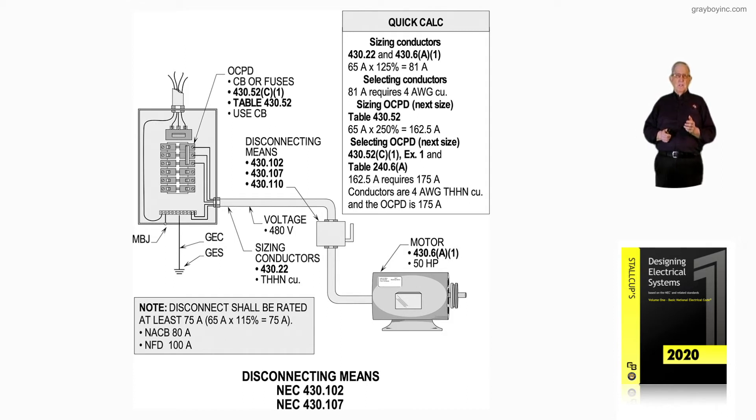Notice the overcurrent device. We start with that to the left at the top, and 430.52C1 and table 430.52 would be the sections used to get a percentage to size a circuit breaker. It would also list what you're choosing: circuit breaker, time-delayed fuse, non-time-delayed fuse, or instantaneous trip settings if permissible. We find all that in our table 430.52.